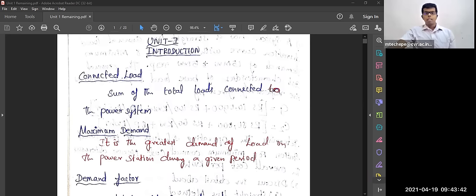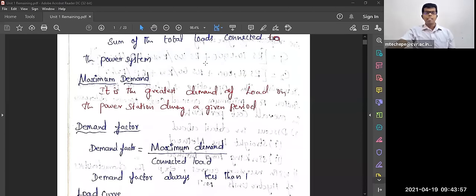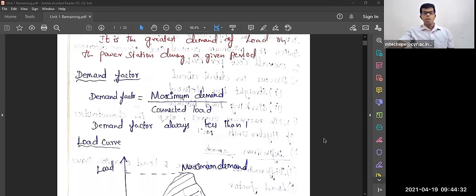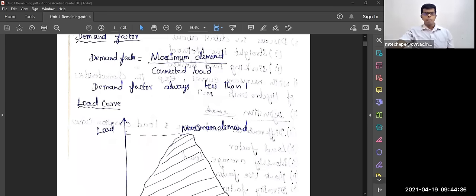Connected load is nothing but the sum of total loads connected to the power system — that is, the sum of all equipment connected to the bus or power system. Maximum demand is the greatest demand of the load on the power system during a given period. Demand factor is maximum demand divided by connected load, and demand factor is always less than one.